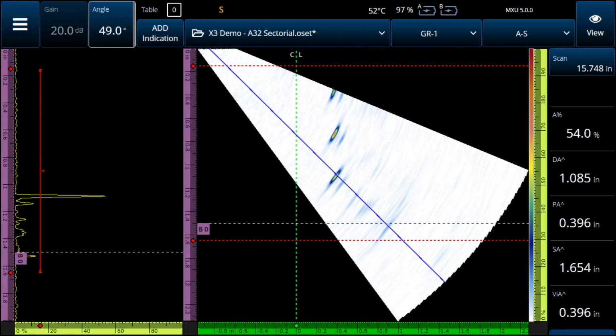Correct. Okay. The display on the left, what we typically call our A scan or analog signal, is the electrical representation of the sound that went through the material and then came back to the transducer. Okay. So we see that in depth and then in strength of the signal or amplitude. Okay. And then in the actual wedge-shaped, what do you call that area, though? The white wedge-shaped area. It's called a sectorial scan.